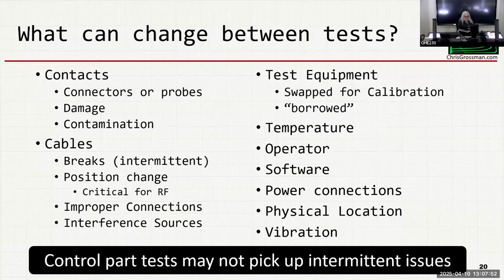Test equipment gets swapped out for calibration. In general, if you have some sort of test set that's being used over time, you don't want to swap test equipment out. You want to keep that same piece of test equipment, and when they check the calibration, put it back in. Don't swap it for another, because that one will be the same. You put it in another, it will be valid, but it'll have some sort of shift, and that shift will show up in your data.